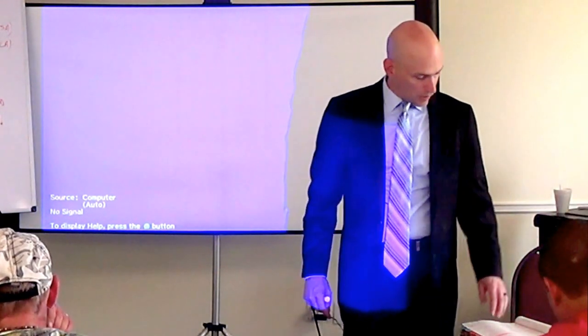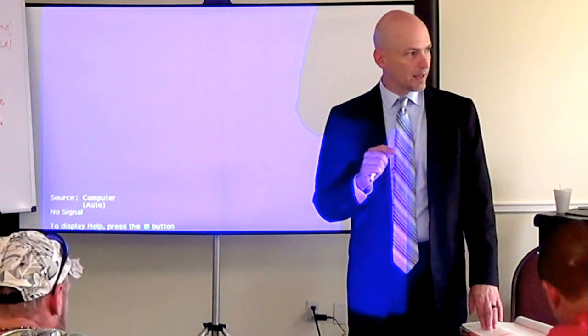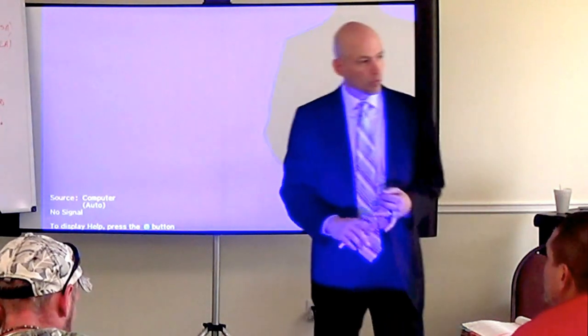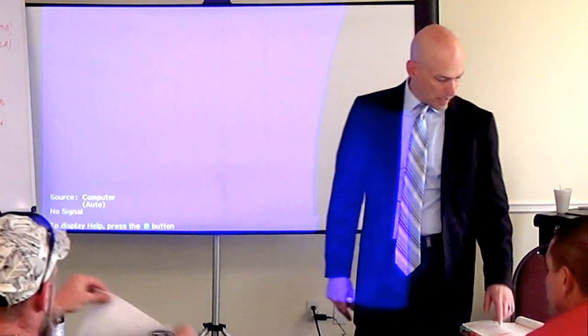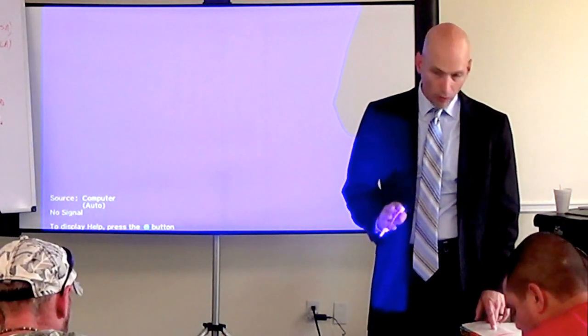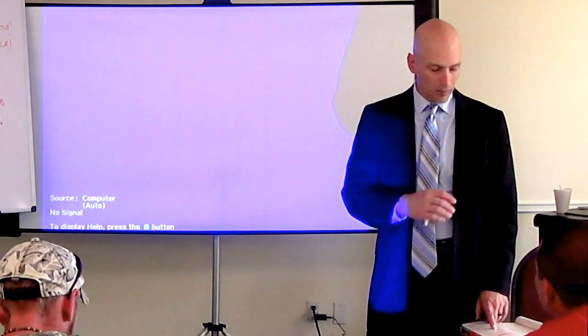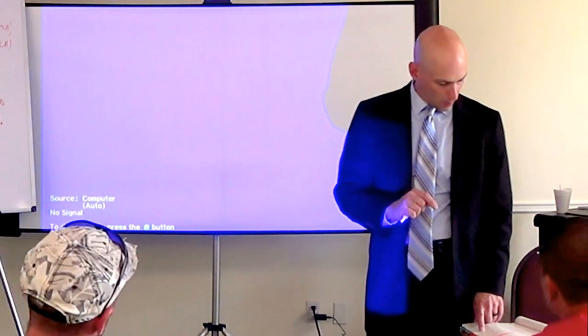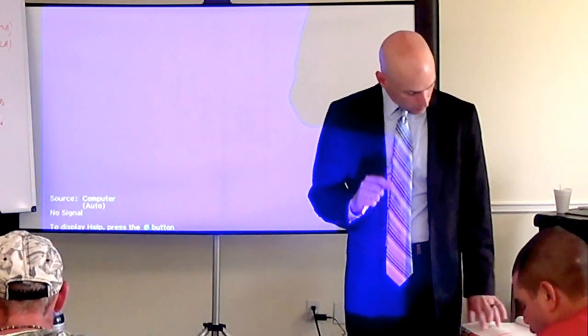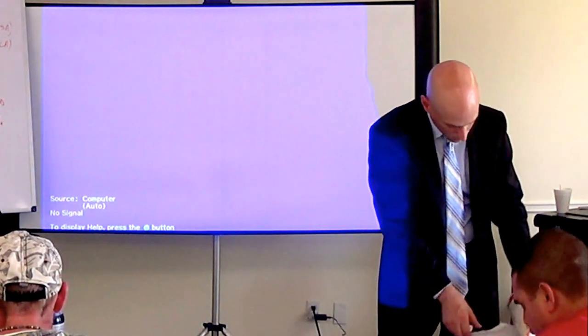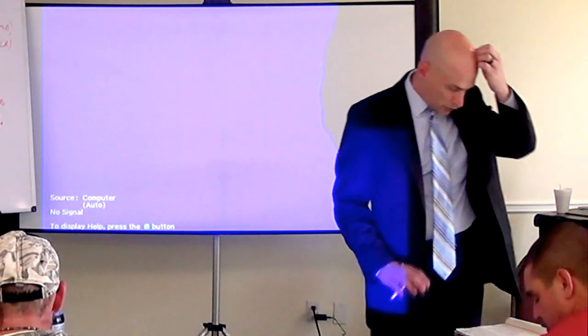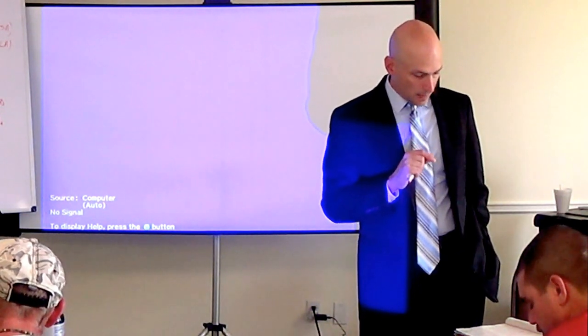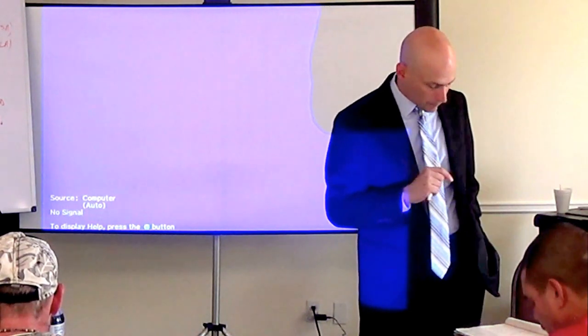So B3 then becomes all your nameplate ratings. And again, what differs here is that we don't have a minimum on the dryer here. We don't use the dryer tables. We don't use the range tables. We just add in the nameplates and keep going. So under B, we'd have a nameplate for anything that's fastened in place, permanently connected or located in a specific circuit. So that's dishwasher, disposal, anything like that, motor load or not. And then ranges, wall-mounted ovens, counter-mounted cooktop units. And then under C, clothes dryers not connected to the laundry circuit. And then additionally, water heaters specifically on number four. And then the last one is, excuse me, under D's. Note four is the nameplate of any permanently connected motors not included in item three. I think you stopped there. You stopped there.